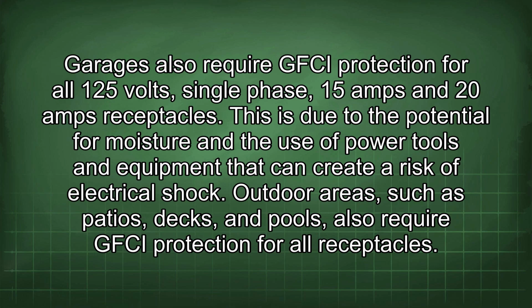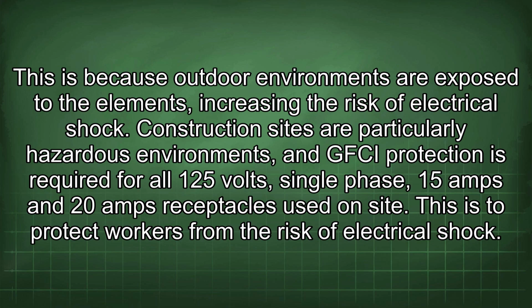Garages also require GFCI protection for all 125 volts, single-phase, 15 amps and 20 amps receptacles. This is due to the potential for moisture and the use of power tools and equipment that can create a risk of electrical shock. Outdoor areas such as patios, decks, and pools also require GFCI protection for all receptacles. This is because outdoor environments are exposed to the elements, increasing the risk of electrical shock.